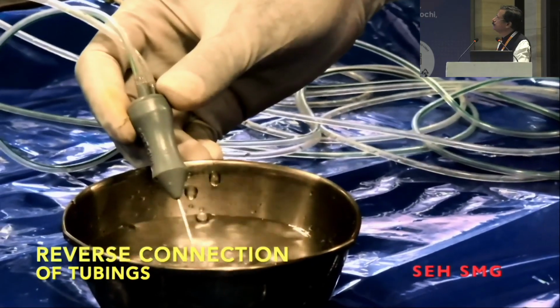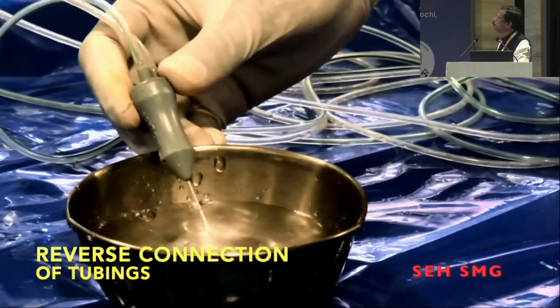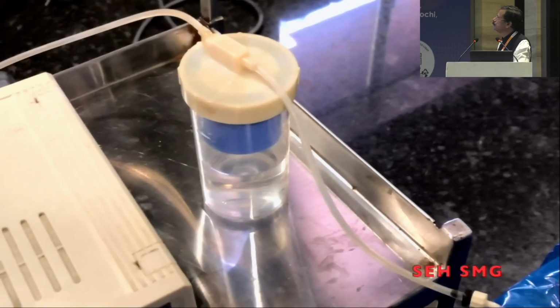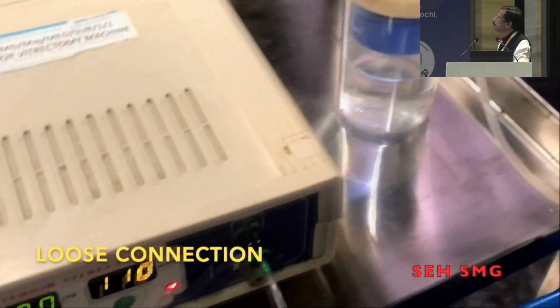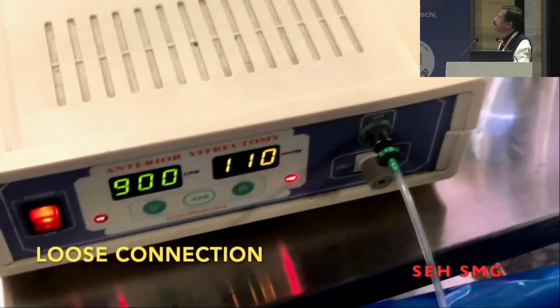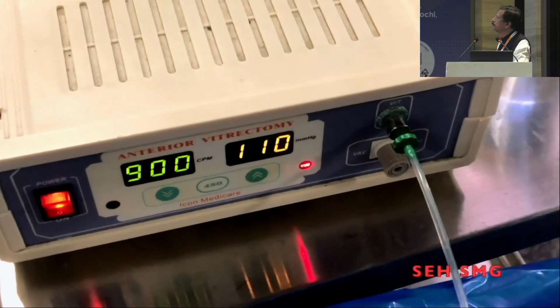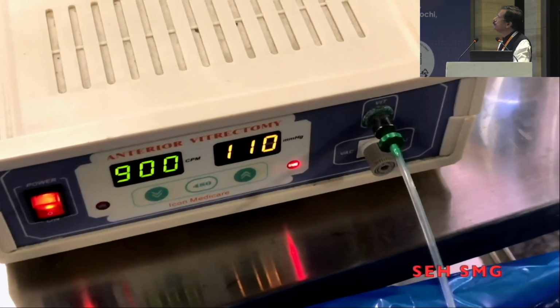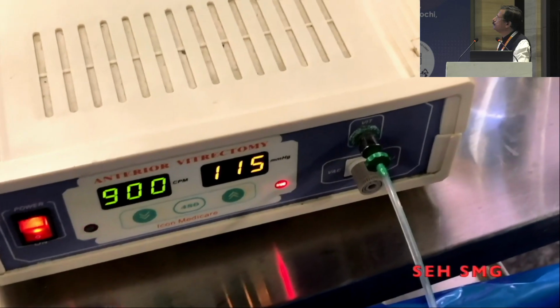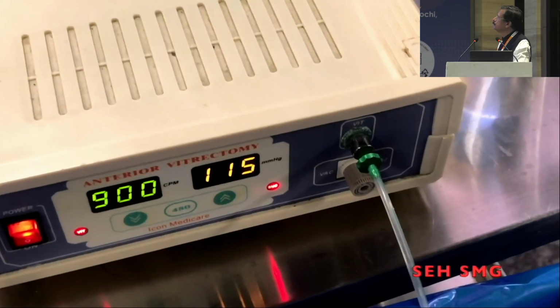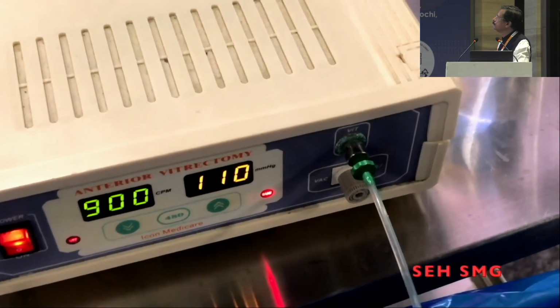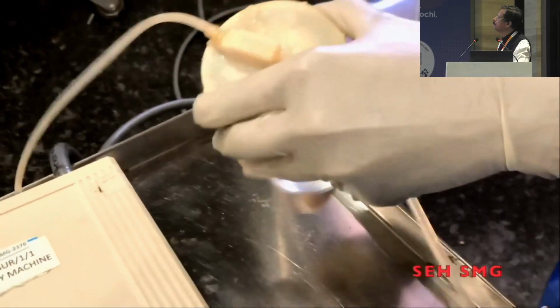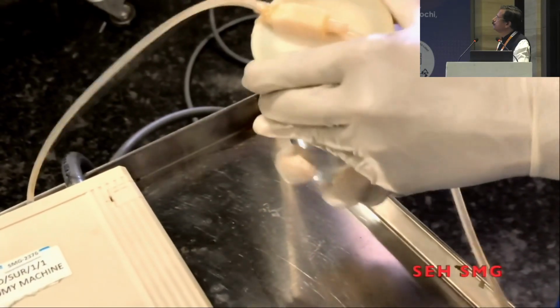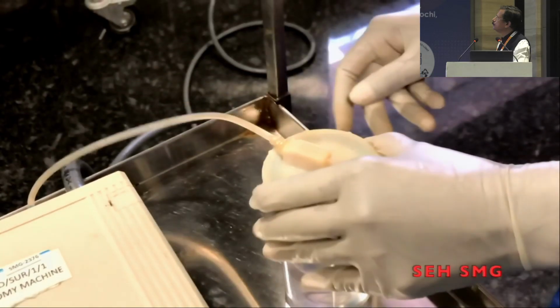If the probe is connected the other way, air bubbles will come out. Now everything has been connected, but the vacuum is not generating. So you have to recheck again. Probably the tip of the vacuum bottle is loosely capped. So you have to tighten the cap and check again.